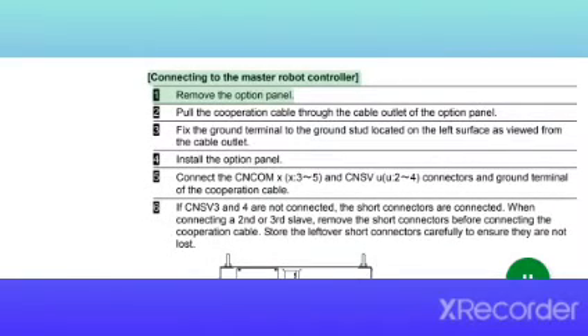Connecting to the master robot controller. 1. Remove the option panel. 2. Pull the cooperation cable through the cable outlet of the option panel. 3. Fix the ground terminal to the ground stud located on the left surface as viewed from the cable outlet. 4. Install the option panel. 5. Connect the CNCOM x3 to x5 and CNSV u2 to u4 connectors and ground terminal of the cooperation cable.